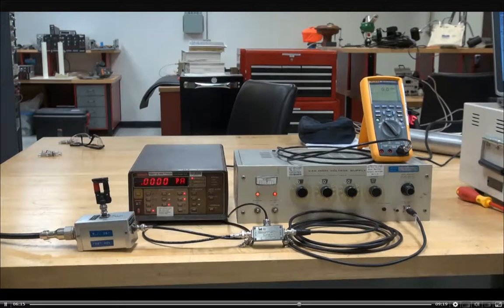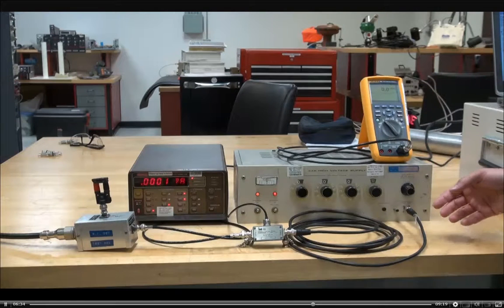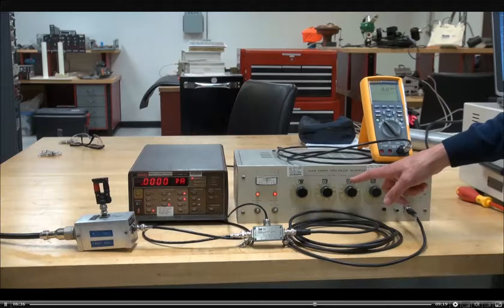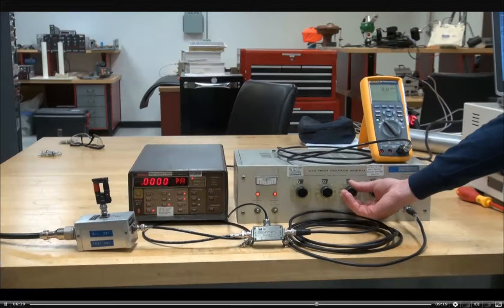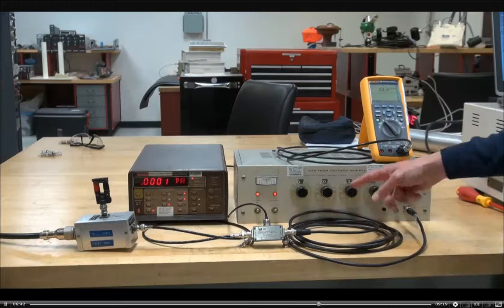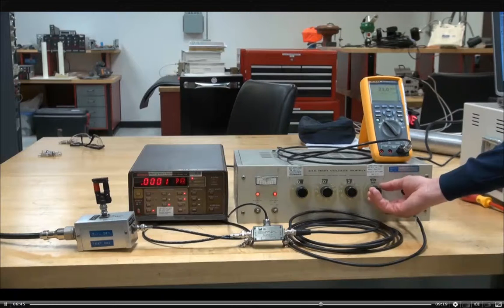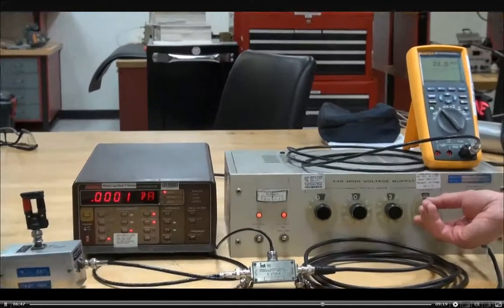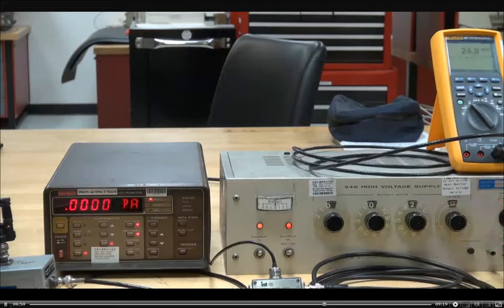Okay, note a minimum of 1 minute must elapse before pressing the zero check push button to extinguish the zero check. And now we are going to set the high voltage power supply for the specified outputs and record the electrometer current reading on attachment 4. Alright, now we're going to go to our chart, which refers us to what voltages we're going to be setting. The first voltage we're setting is 25 volts. So we'll adjust that. For 25, we have a variable knob here. So we have 25 volts set on the high volts power supply.